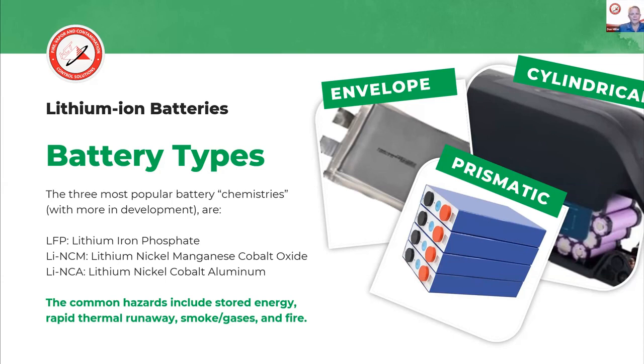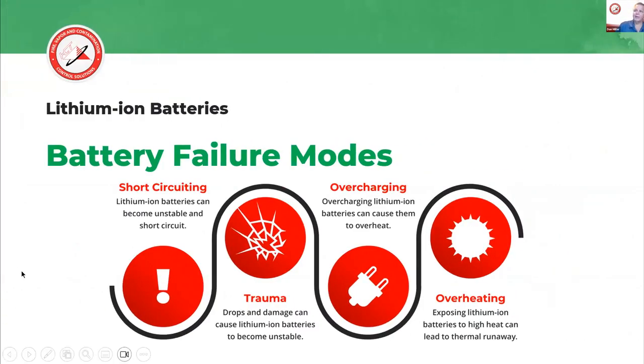There are a few common ways that batteries fail. Lithium-ion batteries have about four different failure modes, but each one has a root cause or several root causes. The first is short circuiting, simply taking the positive terminal and shorting it to the negative terminal. That can happen either externally to the battery, or if the battery has poor battery chemistry, or maybe gets some trauma.